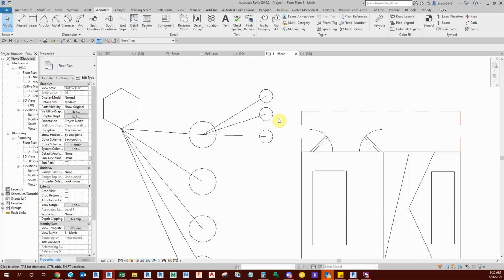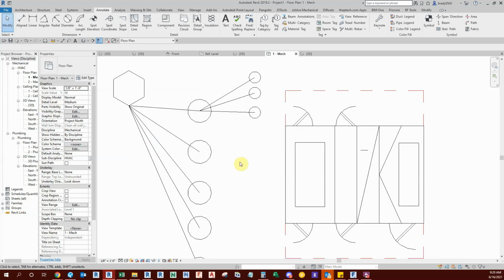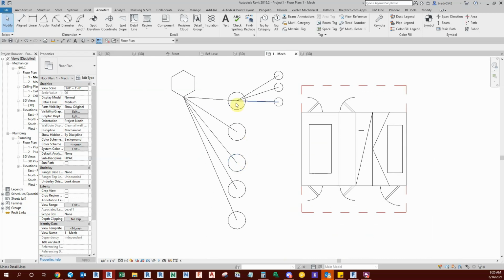And that's how the systems are broken up and actually driven inside the software. On the return side, basically all of your air devices would be target connectors, and the air handler would be the source, even though the flow is backwards. So that's why you have in on the return and out on the air devices, even though the flow is actually going into the return air devices. It's a little confusing, but if you always think about the flow of the information, that's what's important.